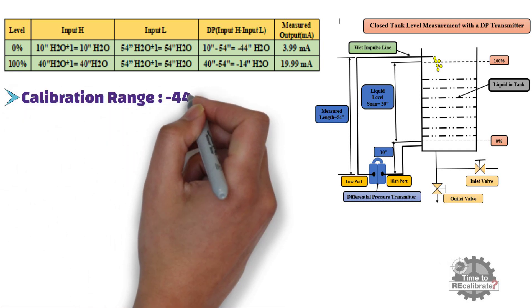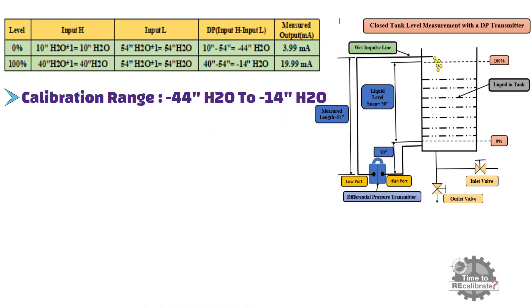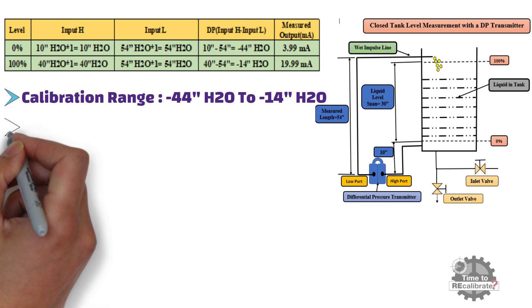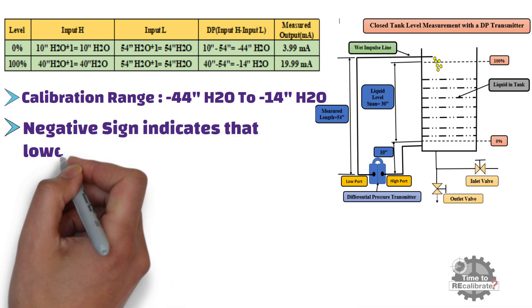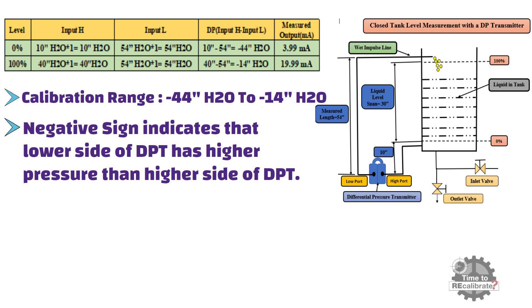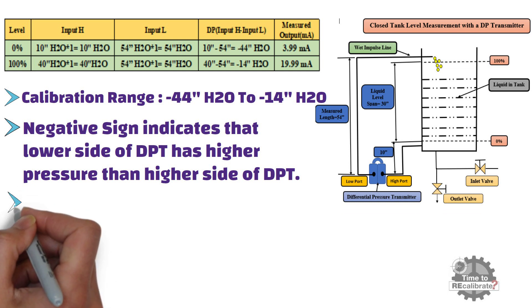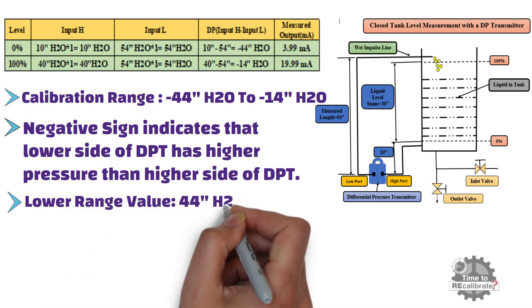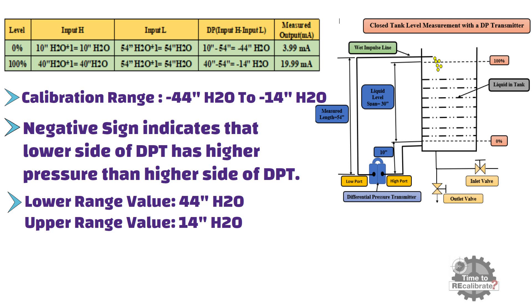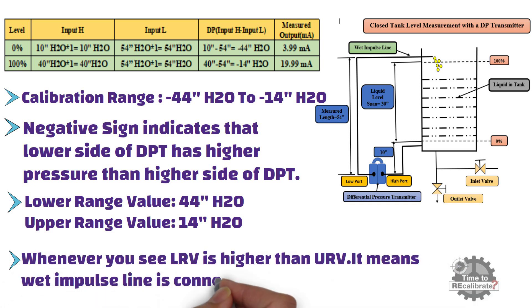As you can see from the table, the calibration range is minus 44 inches H2O to minus 14 inches H2O. Note that you will always get a negative range when measuring level in a closed tank with a wet impulse line. The negative sign indicates that the low port of the DP transmitter has higher pressure than the high port. Since you cannot set a negative calibration range in the DP transmitter, set 44 inches H2O as the lower range value and 14 inches H2O as the upper range value. Whenever the lower range value is higher than the upper range value, it means a wet impulse line is connected to the low port of the DP transmitter.